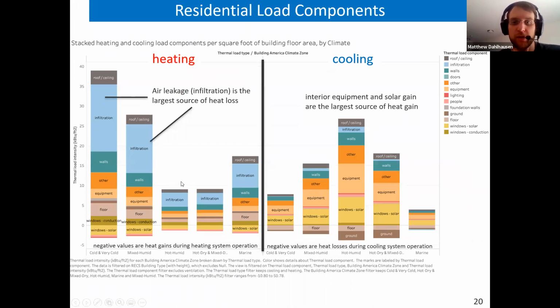We can drill down further to determine the causes of heating and cooling demand. You'll notice the blue section on the left, which is infiltration. Infiltration is half of the heating demand, with conduction losses contributing the rest. Solar gain through windows offsets a bit of the need for heating, and in a well-designed building can offset most or all the heating load, as we'll see in a few slides. For cooling, solar gain through windows and interior equipment causes most of the demand.